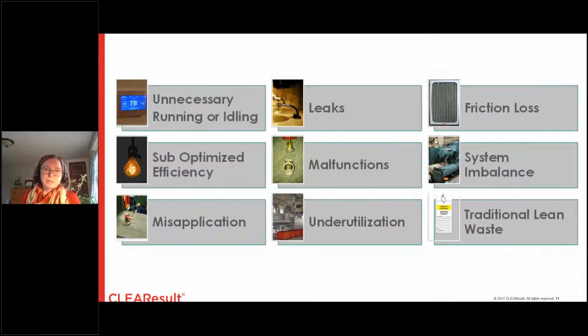Not my favorite term, but it's a nice catch-all bucket for any situation where the equipment you have and the way you're running it is just not right for the job. So think, you've got a 25 horsepower pump, and the job it's doing would have been much better for a 5 horsepower pump. And so the poor thing is just way off its best efficiency point. It's struggling to meet the load in an efficient way. That's one of those sub-optimized efficiency times when you might just need to find a different piece of equipment, or you might need to sequence things differently to get the best efficiency out of your system.